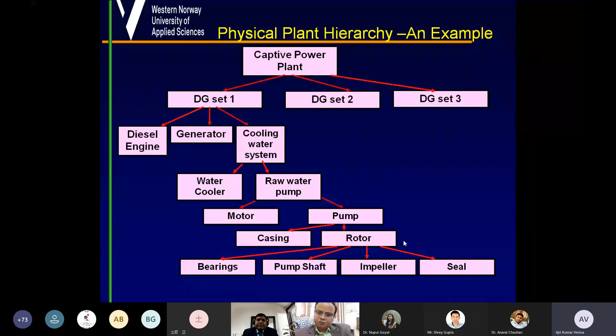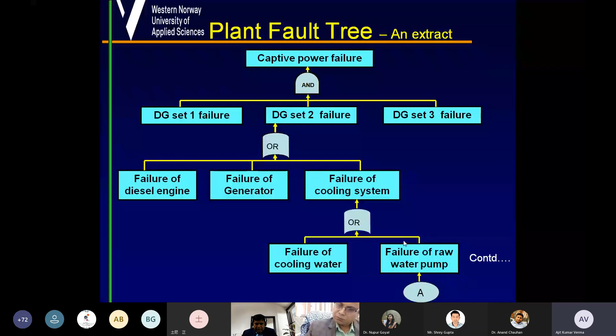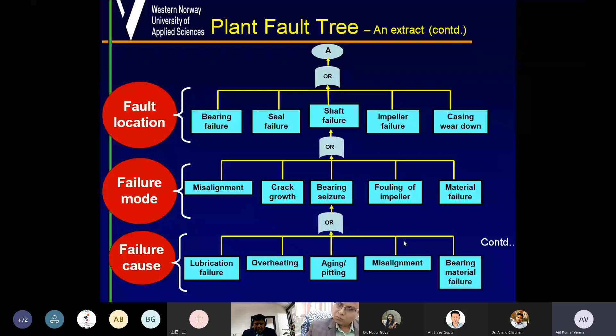Now let's take, for example, the plant fault tree. The captive power failure would happen if all the 3 diesel generator sets fail, and we expand part of the fault tree. For example, the diesel generator set could fail if there is a failure of the diesel engine, failure of generator, failure of the cooling system, failure of cooling water, failure of raw water pump. So eventually we would lead to fault locations, failure mode, and the failure cause, and therefore the kind of sensors that have to be deployed.